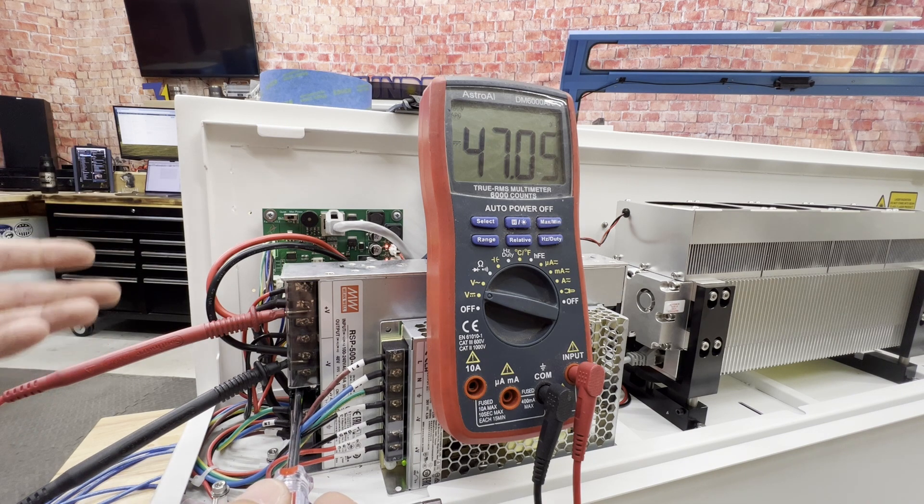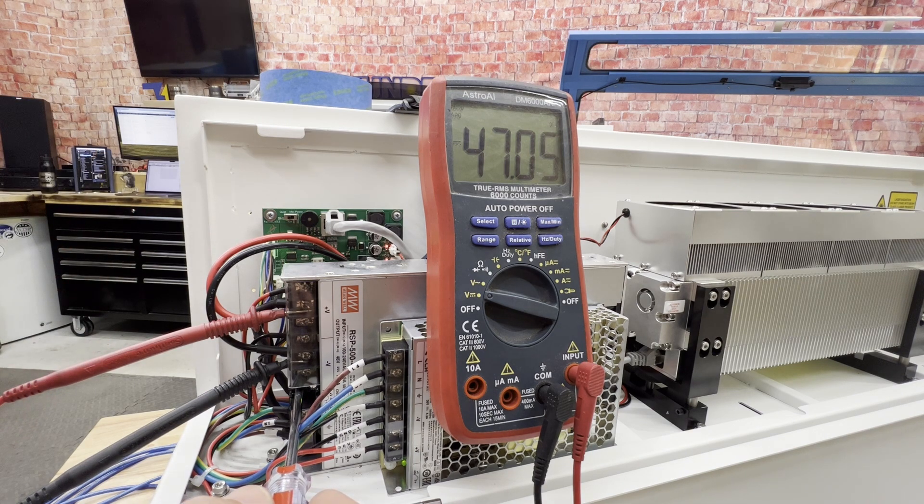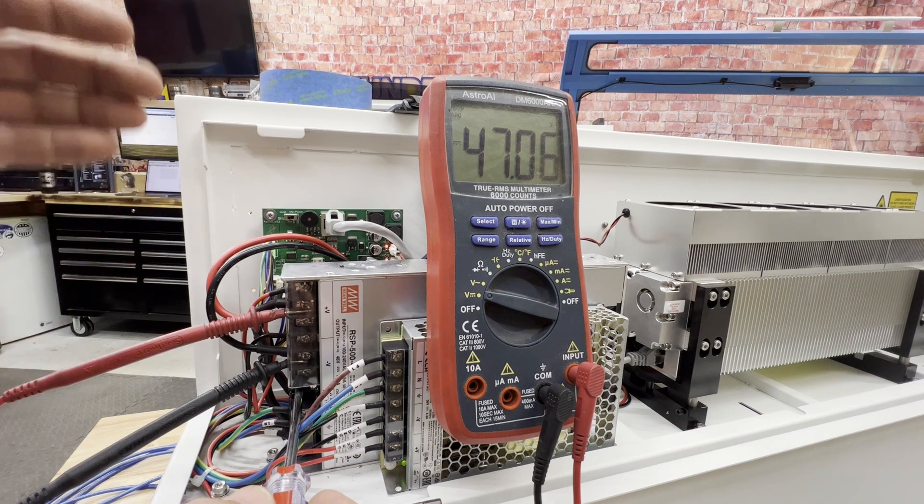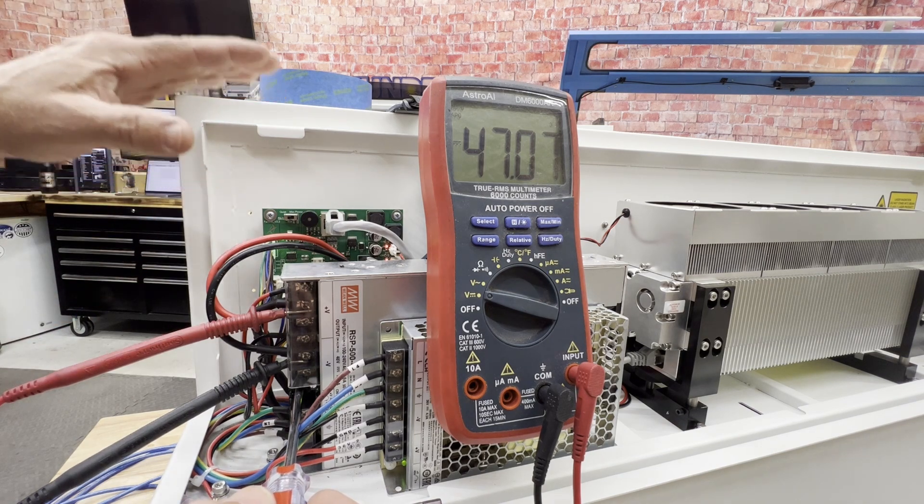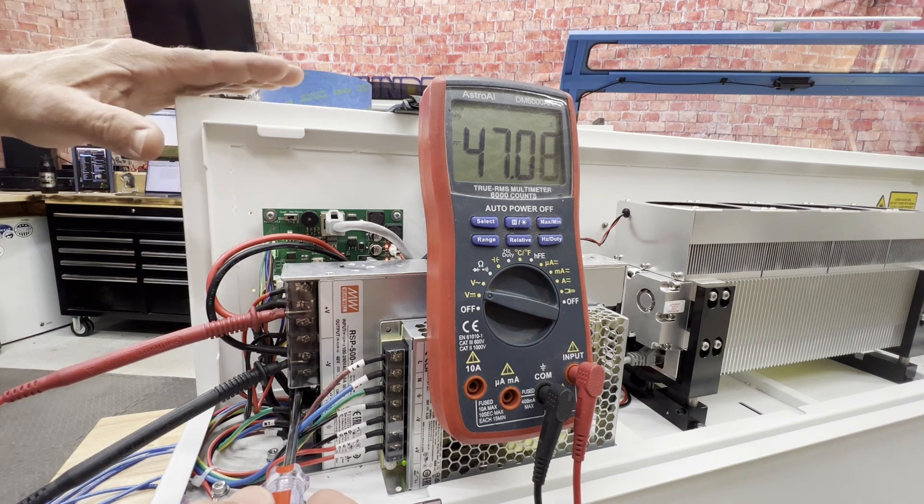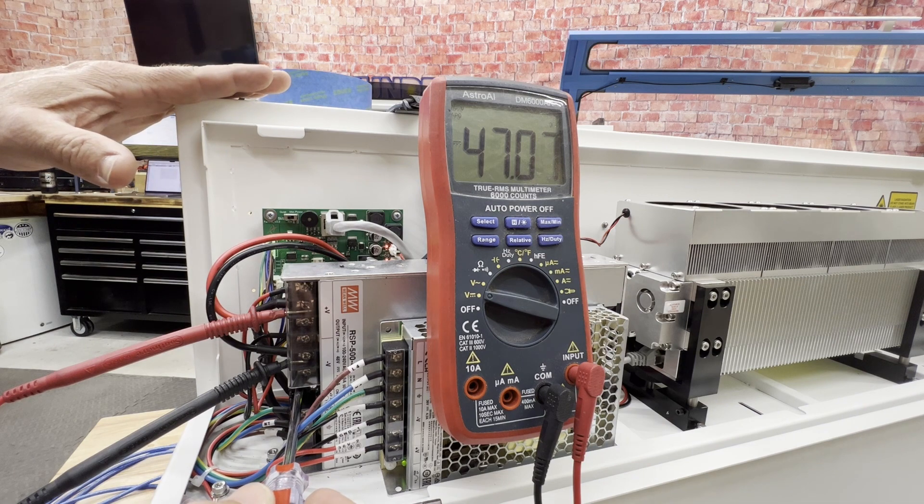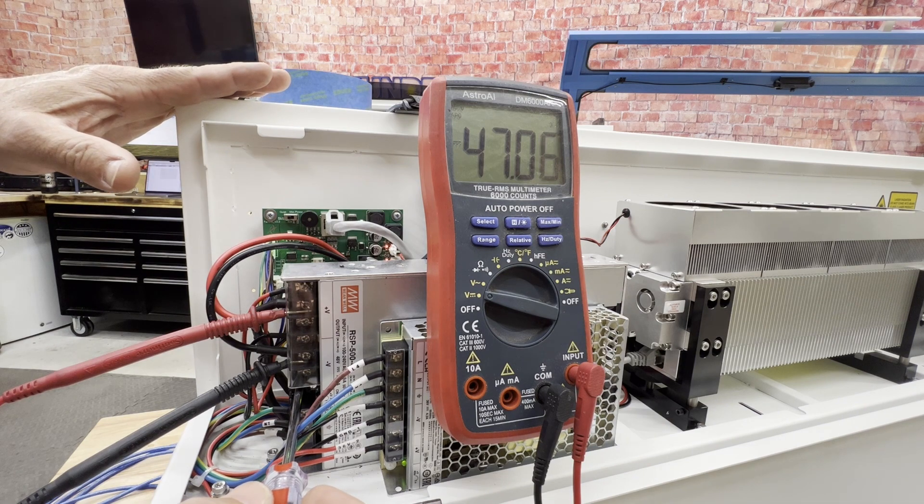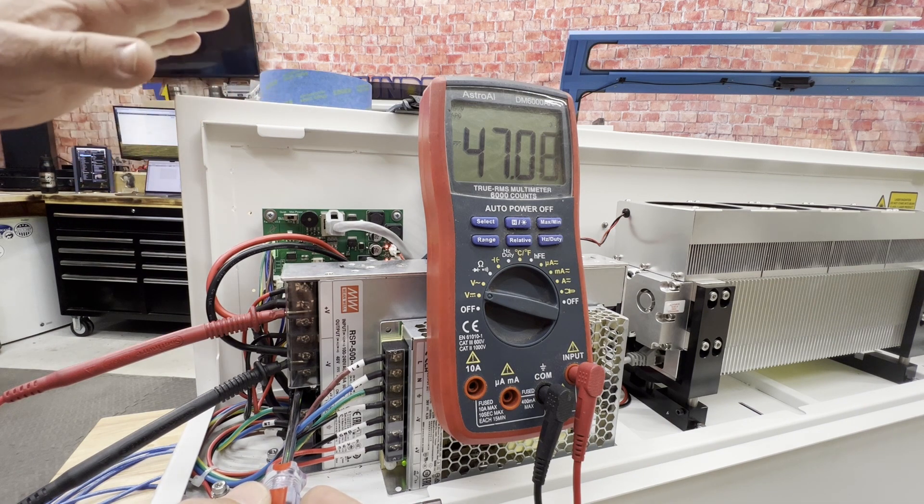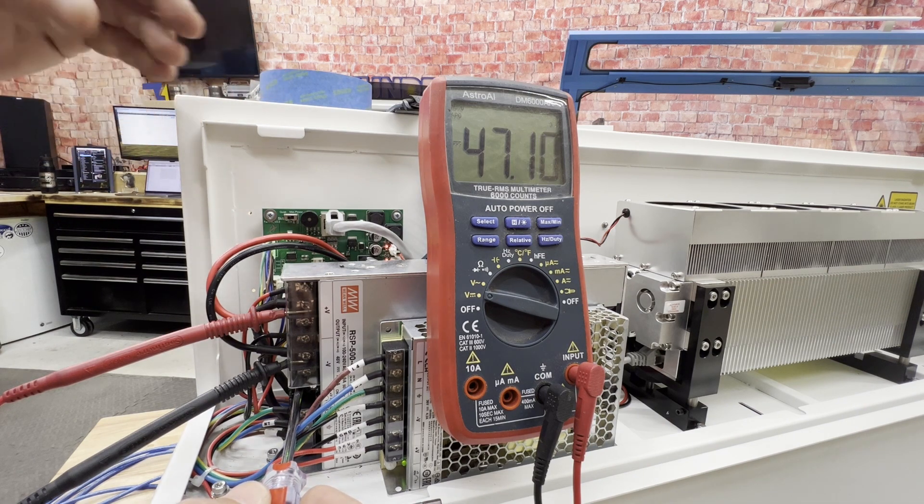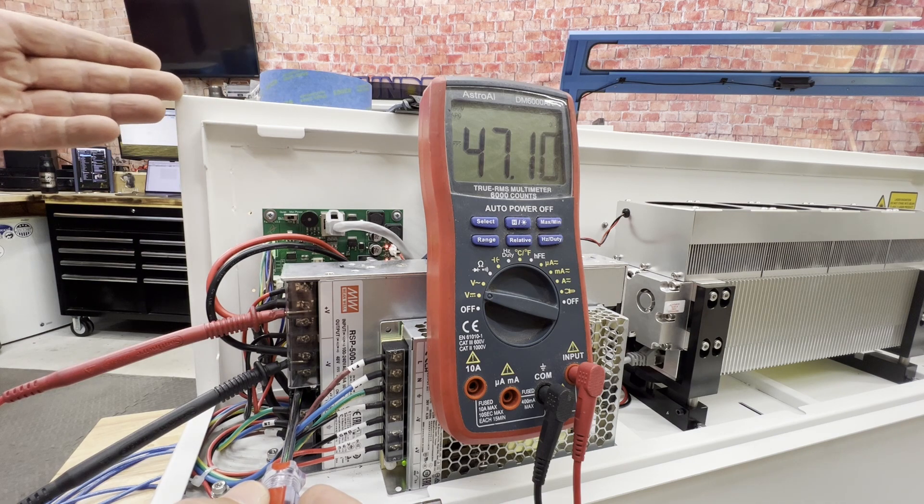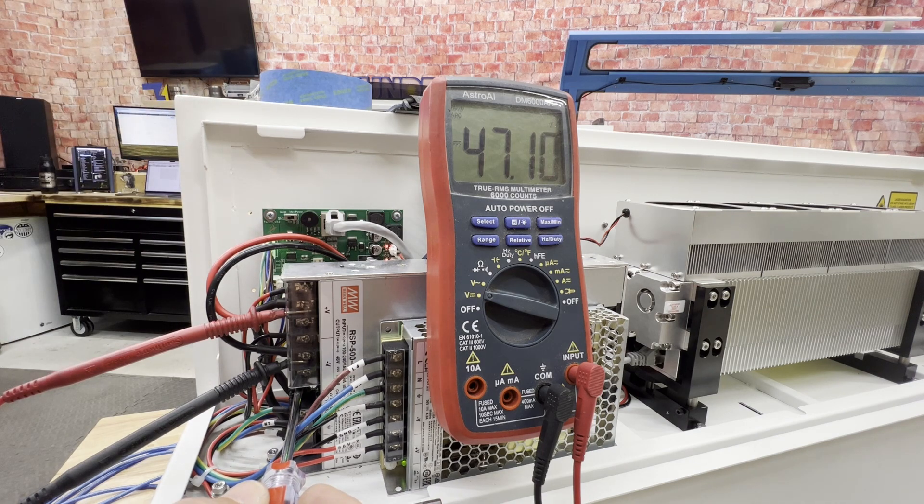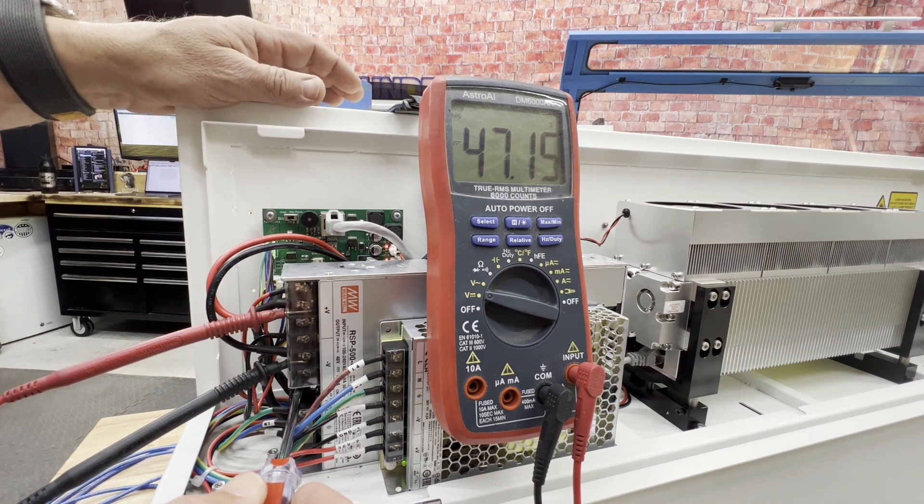Now we don't want to go too low and we don't want to go too high. The fan board and the systems in place are looking for 48 volts, so somewhere in between 47.5 and maybe 49 is where we want to be.